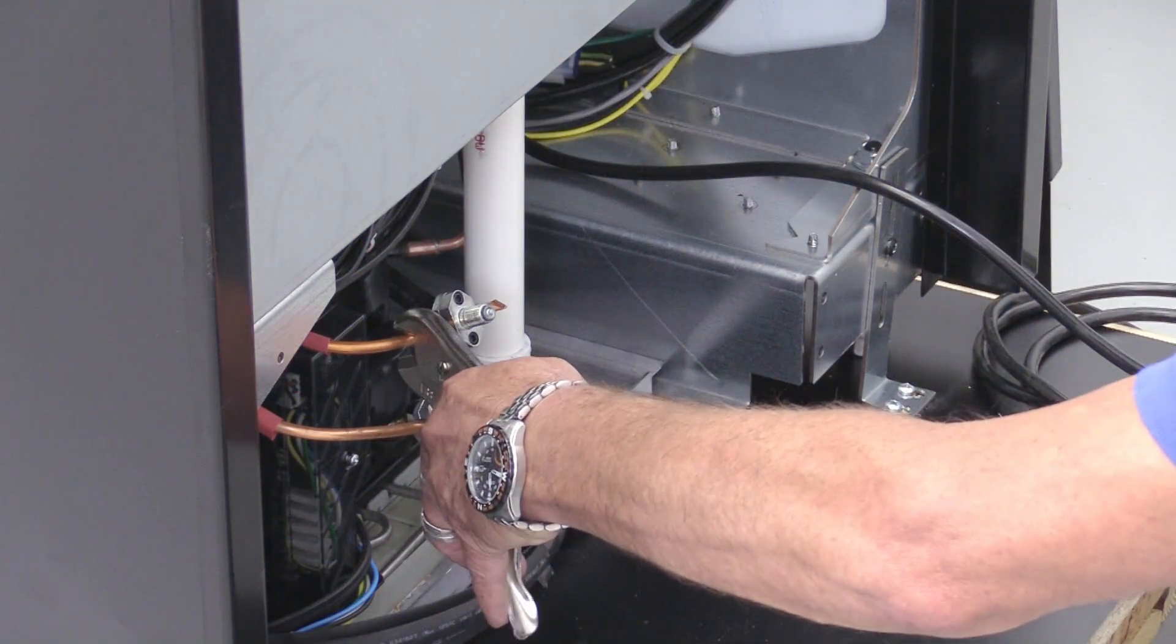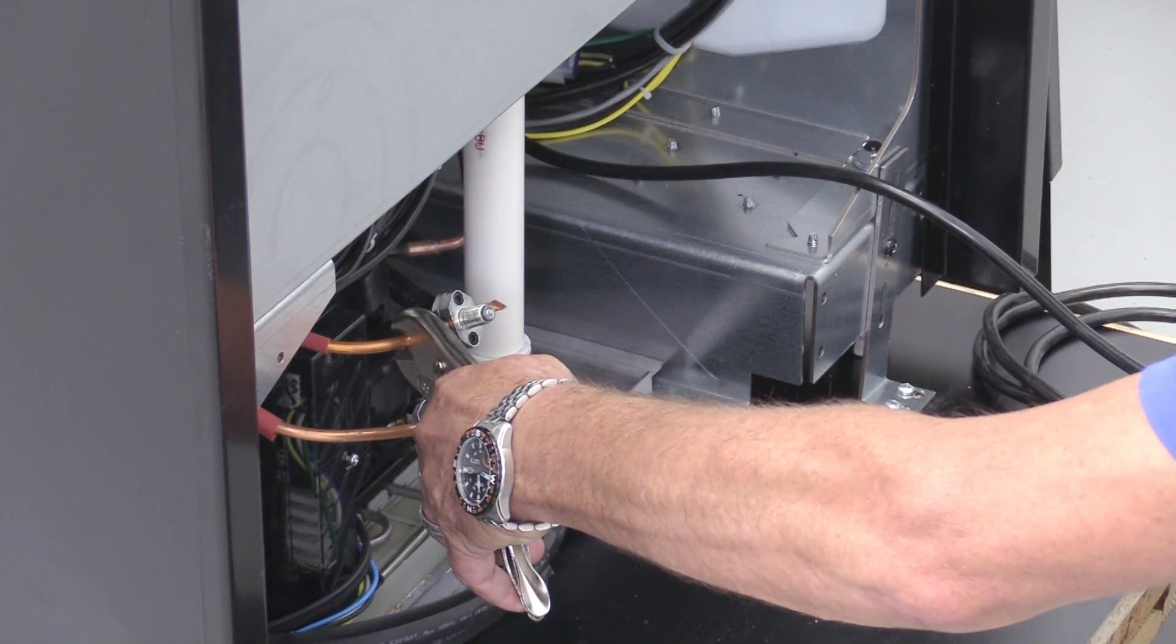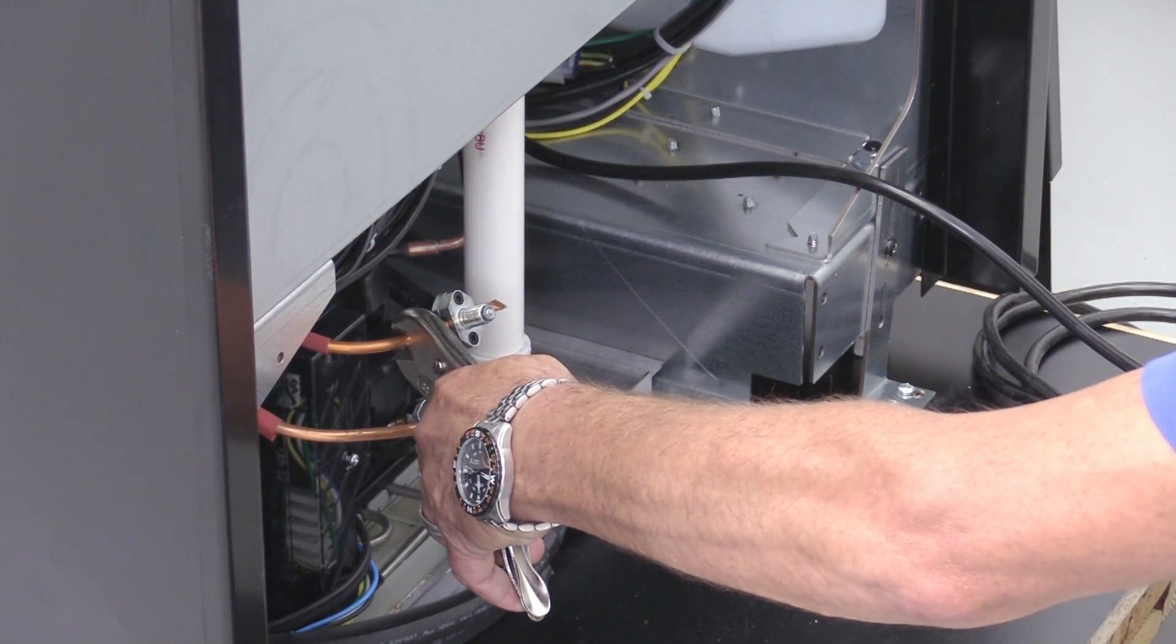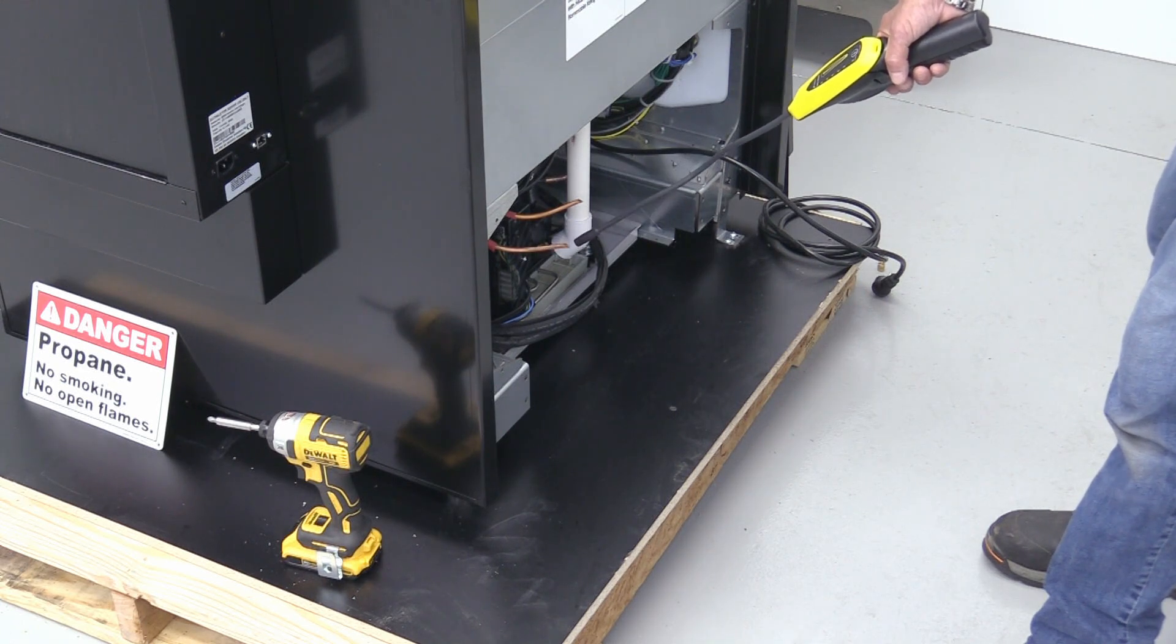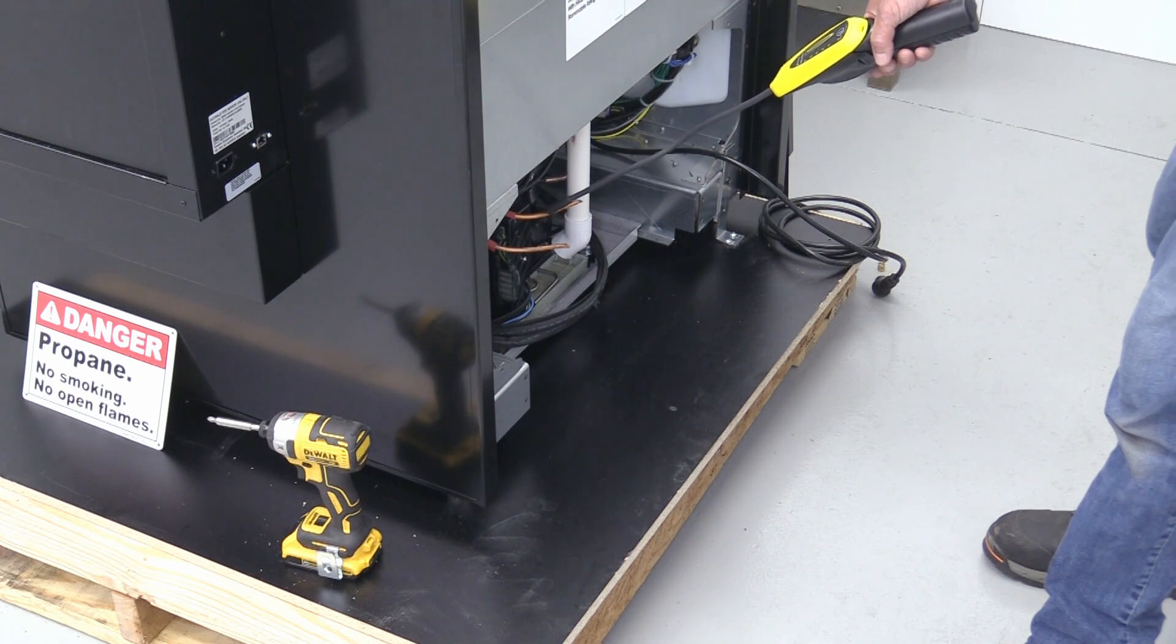Pinch off liquid and suction line process ports. Cut off piercing valves. Check for leaks and braze ends or use a hydrocarbon approved crimp on style cap.